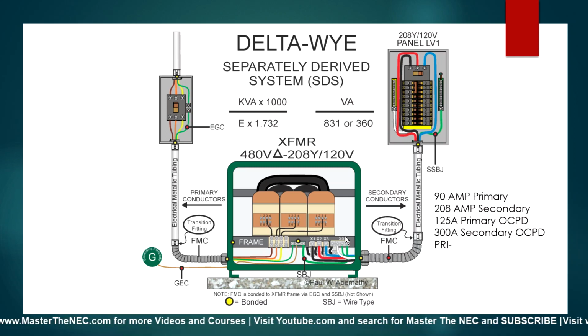Otherwise, you could have one big terminal bus that has the XO and a bunch of lugs, and all of these grounded connections could be made to the XO. It wouldn't be a problem either. But in this case, we're utilizing the allowance under the exception to use a wire type system bonding jumper, and then I can use that to connect this equipment grounding bus lug over to the XO. And it means that I can take the GEC to this location rather than everything having to go to here. Okay?